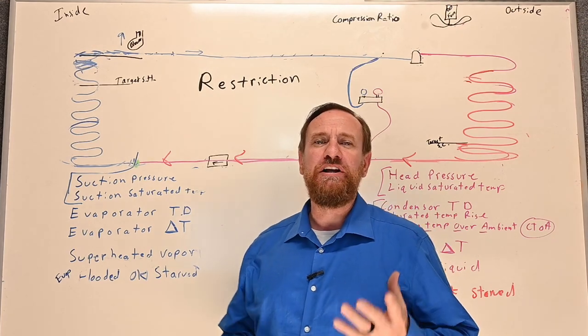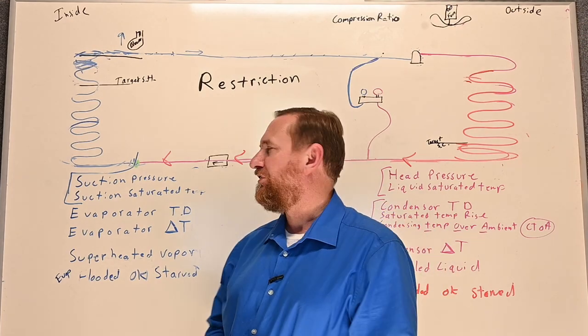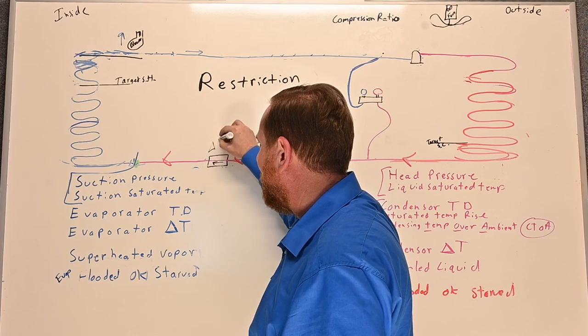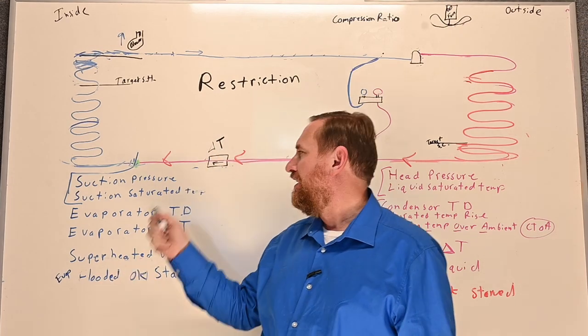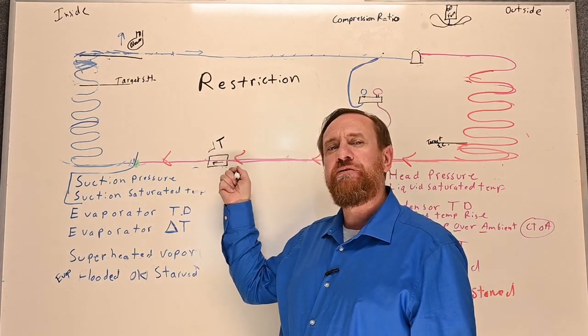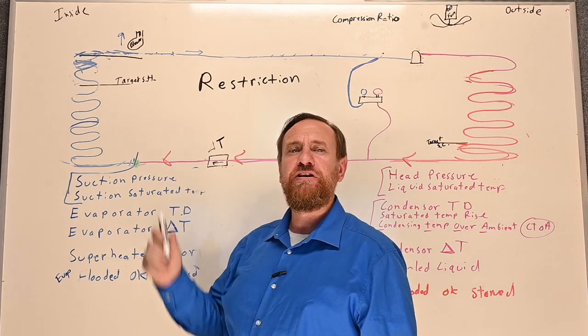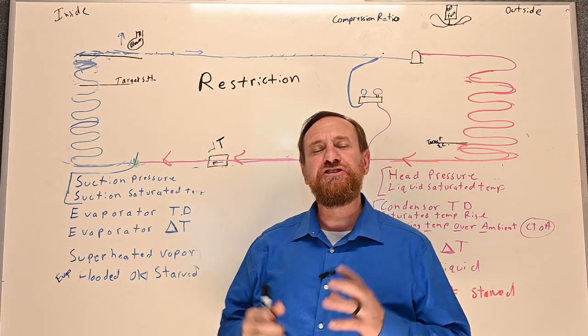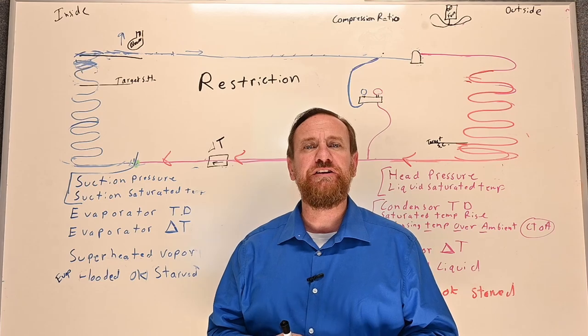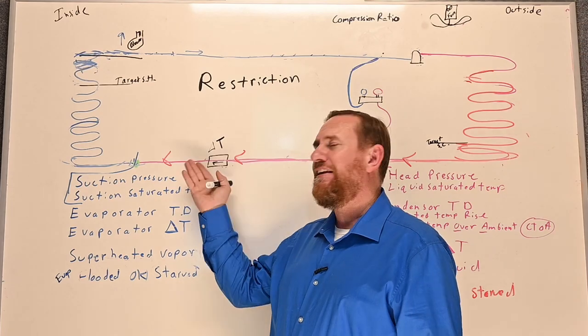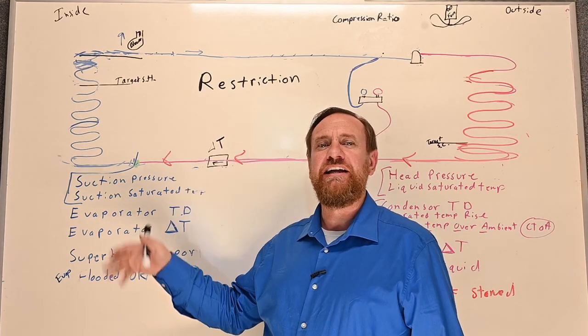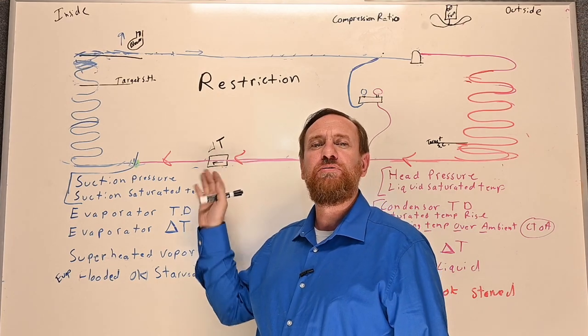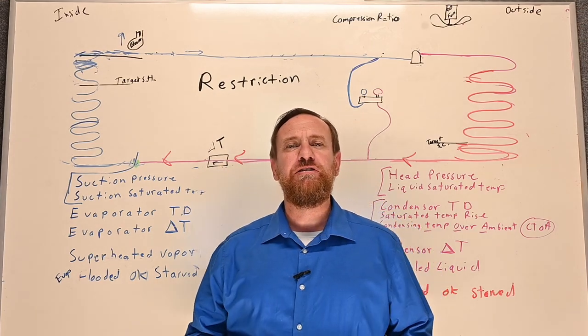We'll start with the easiest one: the filter dryer is clogged up. We'll check for a delta T across the filter dryer — the temperature of the refrigerant coming in versus the temperature coming out. Those two numbers should be very close together, with very little if any temperature drop. As you start seeing a temperature drop, you know that is where your restriction is.